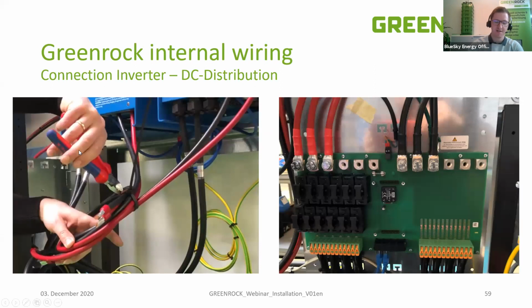Each battery inverter has a plus and minus battery connection, and this cable needs to be connected to the main box. Inside the main box is a combiner board where all the battery stacks are connected, and where all the inverters need to be connected too. This is also how it looks inside a combiner box. If you don't install our GreenRock home system but use a different inverter, or your own Victron inverter, that's also possible—it just looks like that.